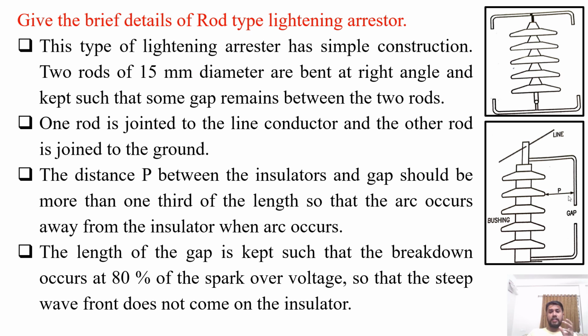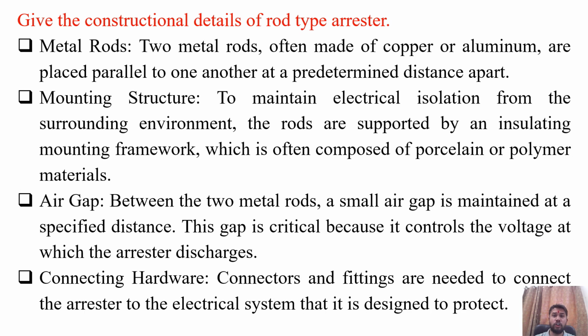The distance P between the insulator and the gap should be more than 1/3 of the length of this insulator, so that the arc occurs away from the insulator. So the arc takes place between these two electrodes, between this gap, and it is safe away from the insulator disc over here. The length of the gap is kept such that the breakdown occurs at 80% of the spark over voltage, so that the steep wave front cannot come on this insulator disc, and this is how this rod gap protects against the lightning surges. Give the constructional details of rod type arrester.